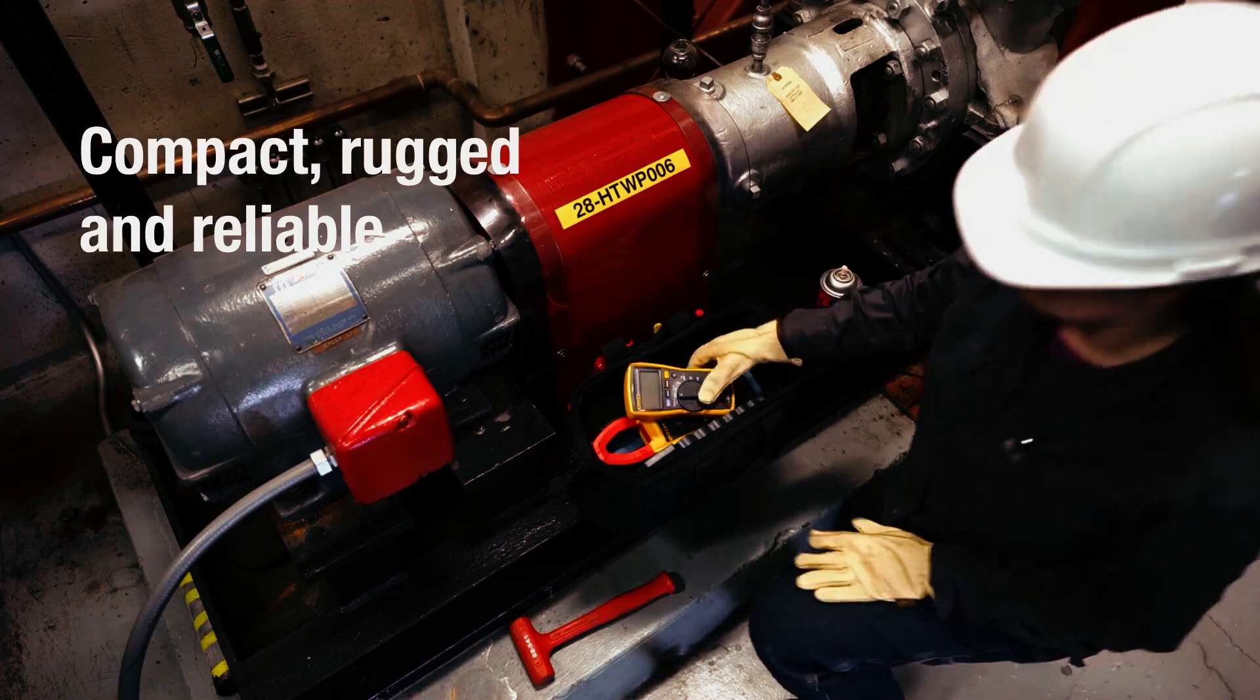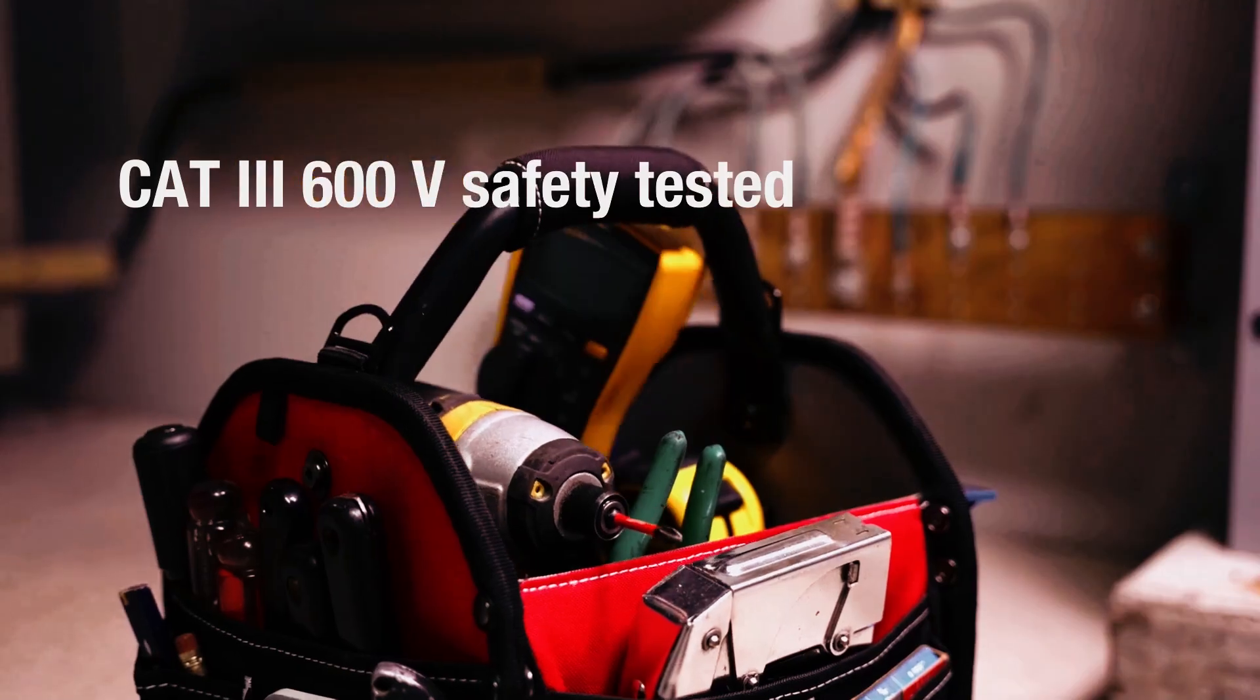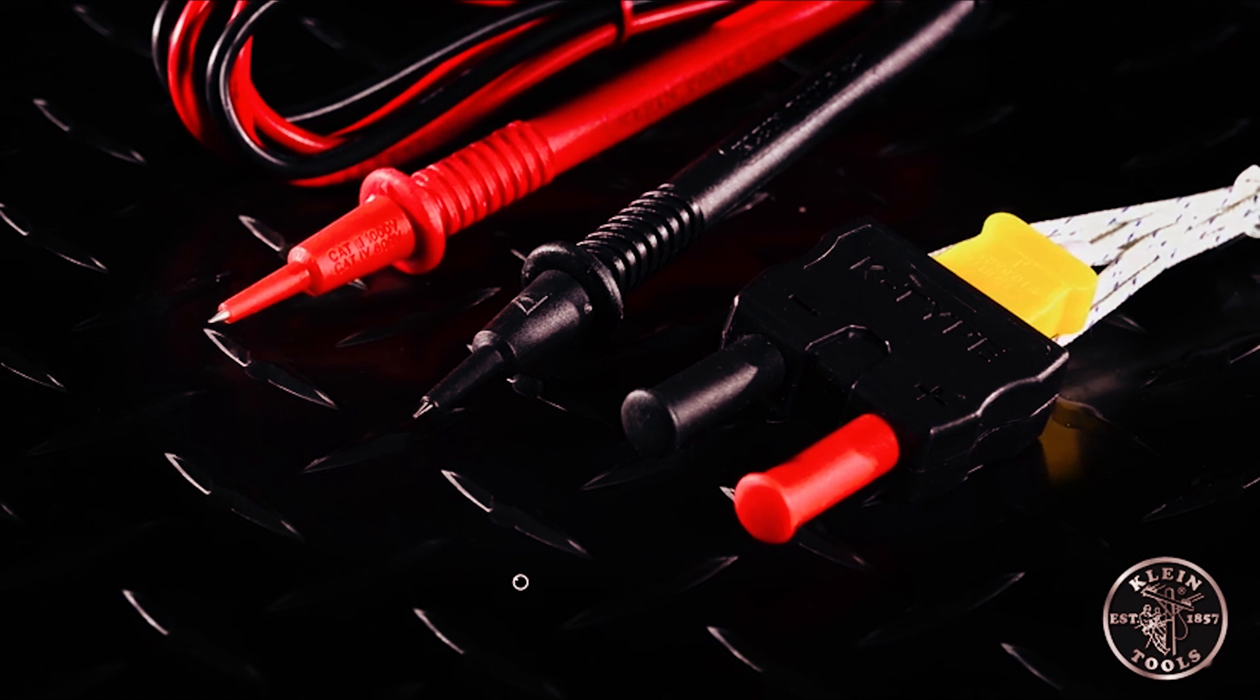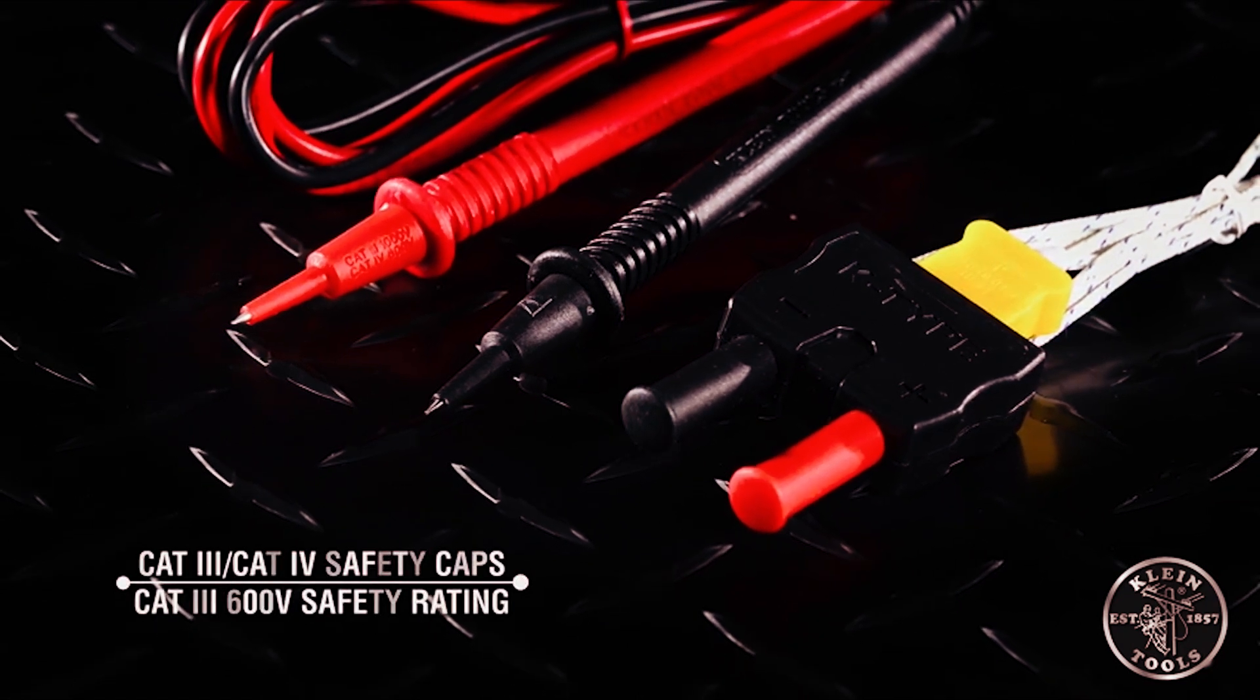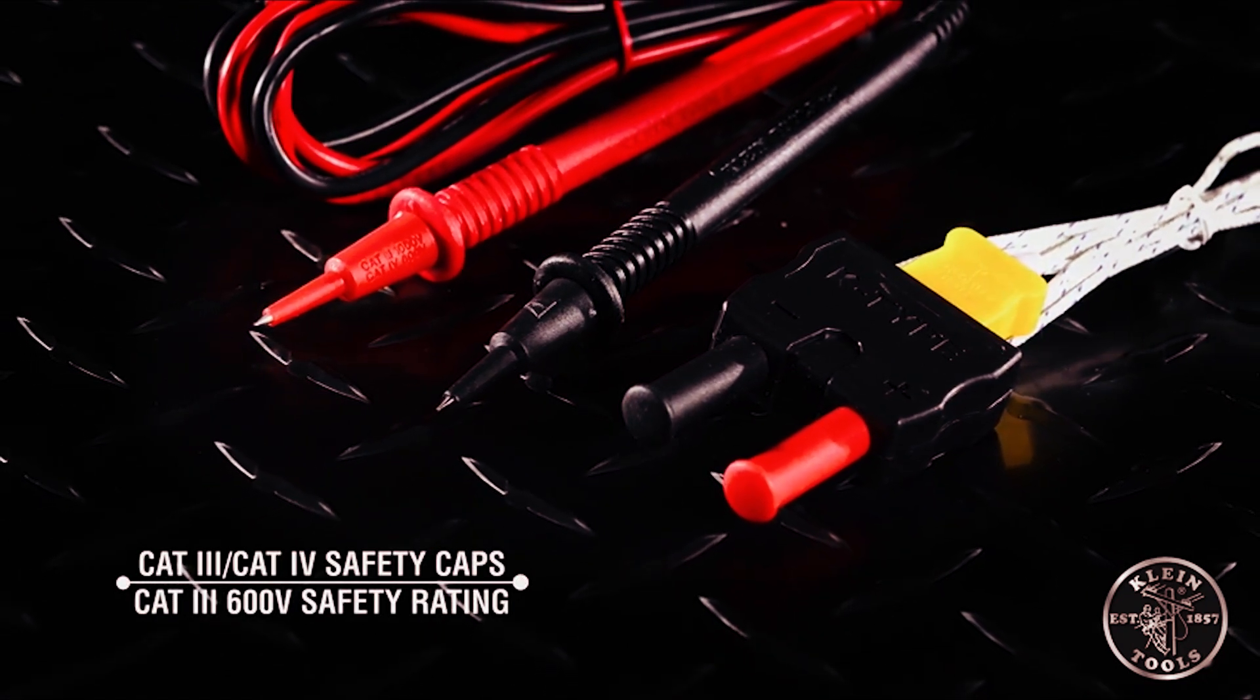If you're working with residential or light commercial systems, a CAT 3-rated multimeter will do. But if you're dealing with industrial or high-voltage systems, you'll need a CAT 4-rated tool.